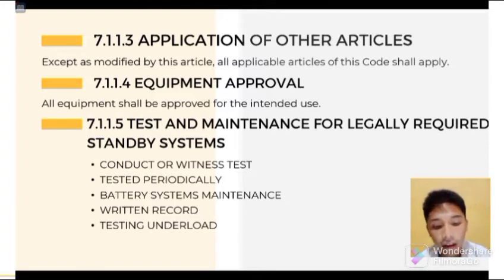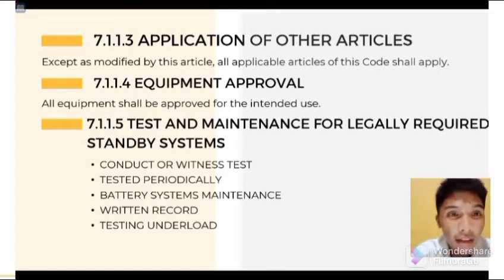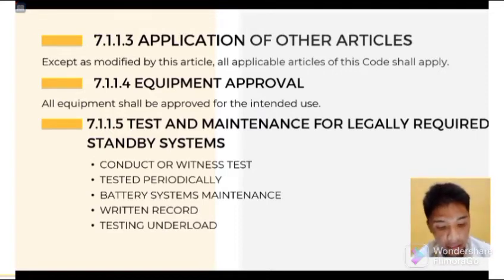Letter C. Battery systems maintenance. Where batteries are used for control, starting or ignition of the prime movers, the authority having jurisdiction shall require periodic maintenance. Letter D. Written record. A written record shall be kept on such tests and maintenance. Letter E. Testing under load. Means for testing legally required standby systems under load shall be provided.